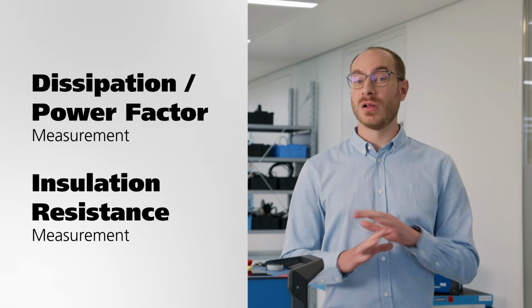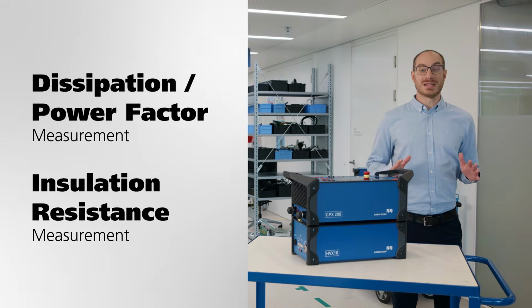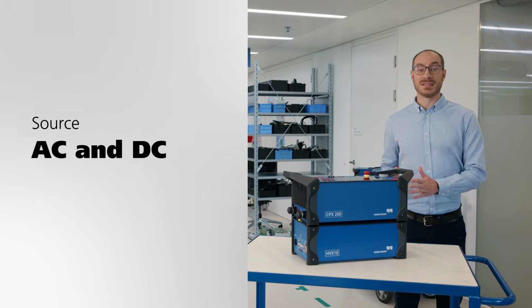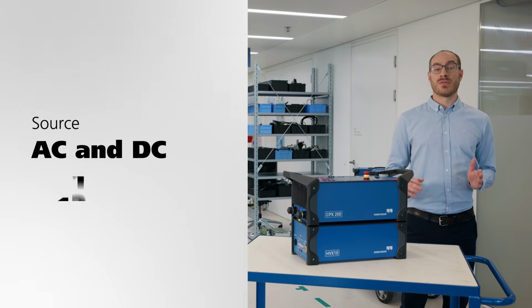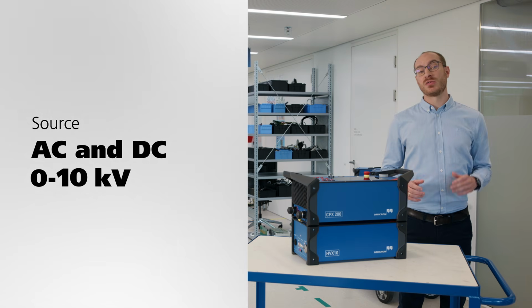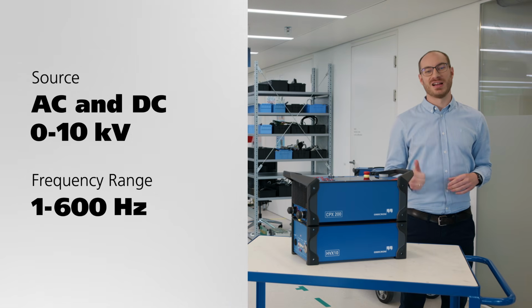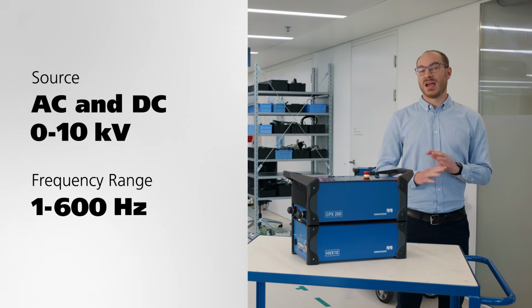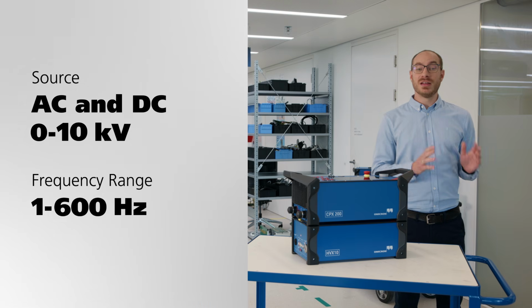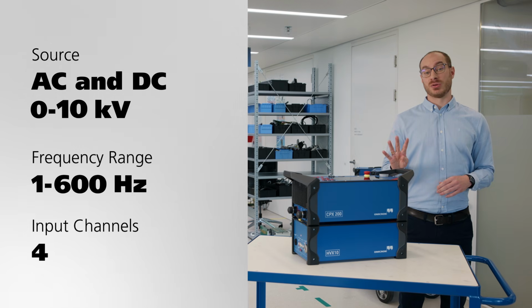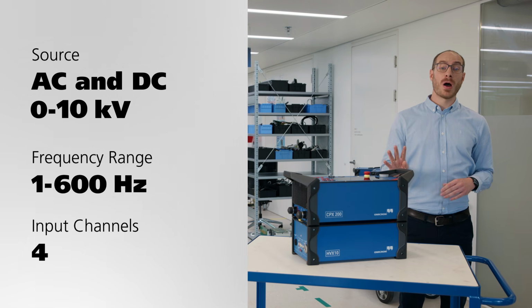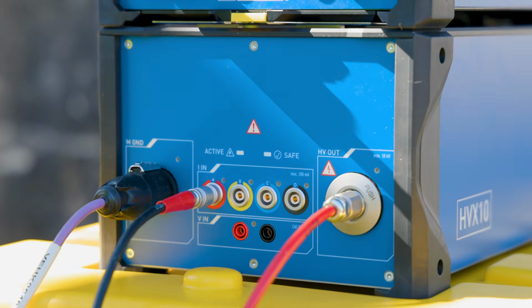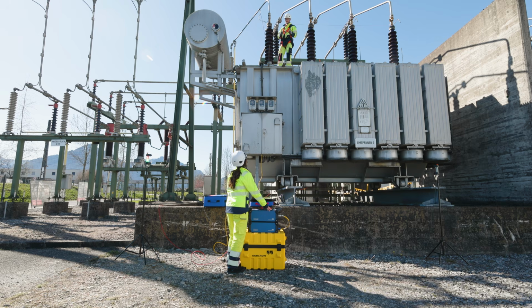That's why we took a totally new approach with the HVX 10. It seamlessly integrates both an AC and DC source, delivering precise measurements from 0 to 10 kV in a frequency range from 1 to 600 Hz from a single output. Fast, easy, and without rewiring. In addition, HVX 10 has 4 measurement input channels. This means you can measure 4 power transformer bushings simultaneously and get more diagnostic insights than ever before. This combination of the two most prominent insulation diagnostic tests is a giant leap for the industry and absolutely unique.